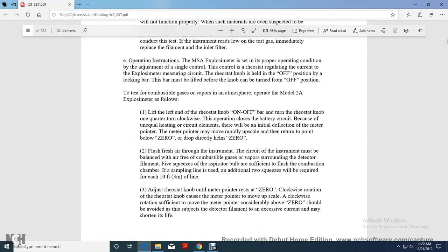Operating instructions for the MSA explosimeter: set for proper operating condition adjustment. The single control is the rheostat regulating current in the explosimeter measuring circuit. The rheostat knob is held in the off position by the locking bar. The bar must be lifted before the knob can be turned from the off position. This is for testing combustible gas and vapor in the atmosphere.